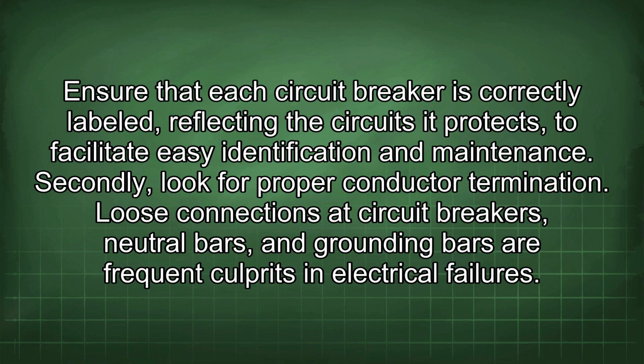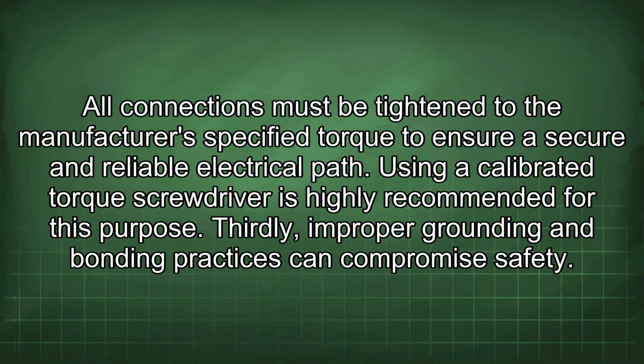Secondly, look for proper conductor termination. Loose connections at circuit breakers, neutral bars, and grounding bars are frequent culprits in electrical failures. All connections must be tightened to the manufacturer's specified torque to ensure a secure and reliable electrical path. Using a calibrated torque screwdriver is highly recommended for this purpose.